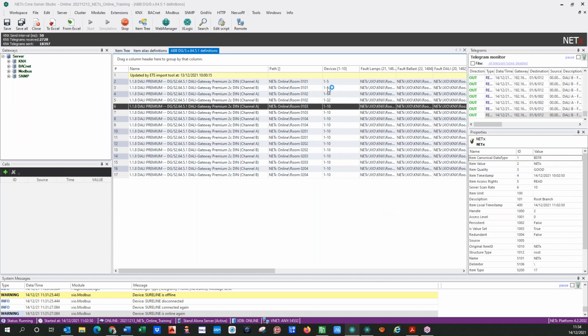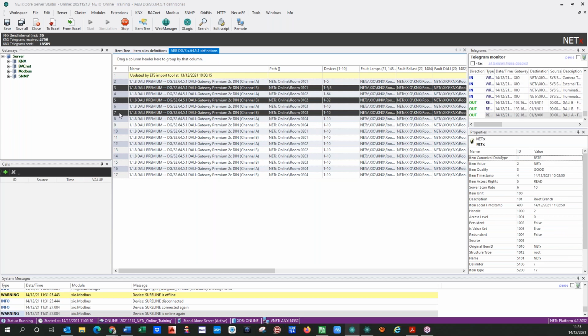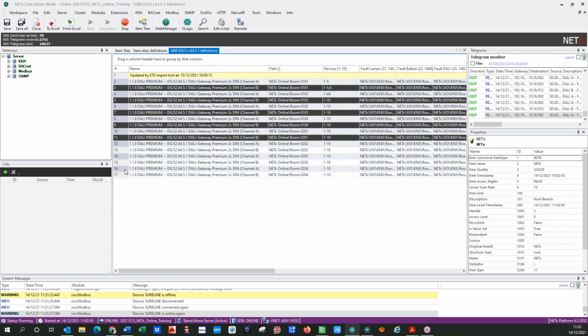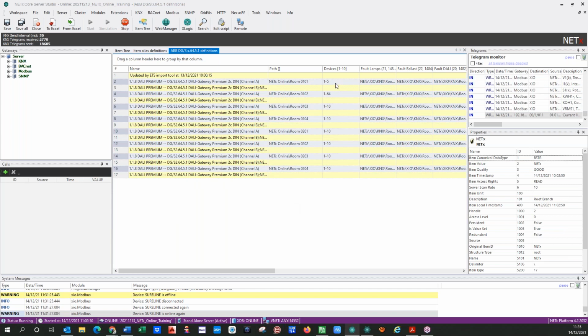The only thing to do is to check these devices from every single channel of your DALI gateways to include which ballasts you have to monitor. Every one of these ballasts is one data point to count in your license. So if you are not using, for example, channel B in all these elements, you will save several data points if you just put them to sleep.